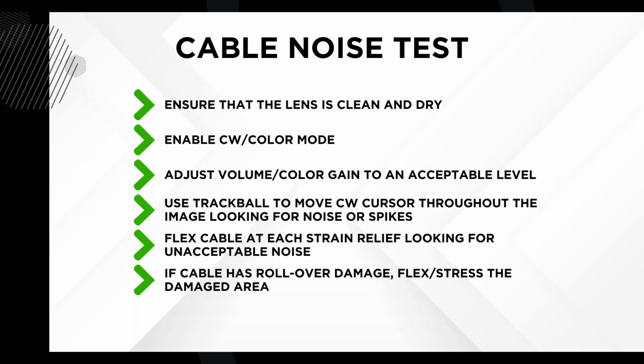So we can check the color box too. I don't know if it'll spike or not. Yep, there it is. You see a spike? So that indicates, sorry, a defective transducer. And that's one of the reasons why we want to go through and do these quality assurance tests on each individual transducer. It can take some time.